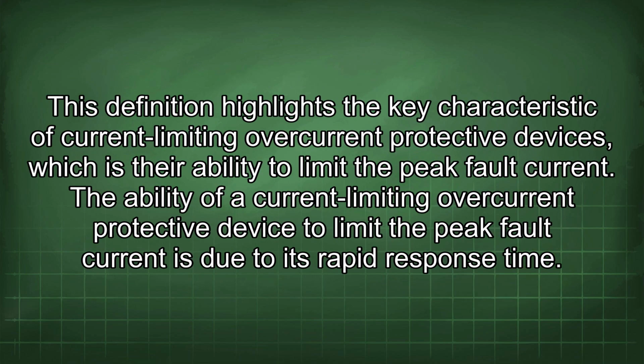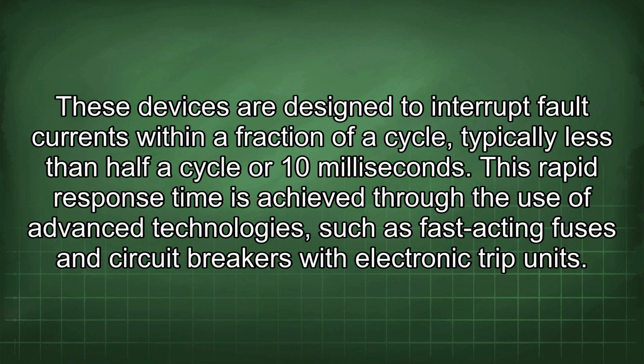This definition highlights the key characteristic of current-limiting overcurrent protective devices, which is their ability to limit the peak fault current. The ability of a current-limiting overcurrent protective device to limit the peak fault current is due to its rapid response time. These devices are designed to interrupt fault currents within a fraction of a cycle, typically less than half a cycle or 10 milliseconds.